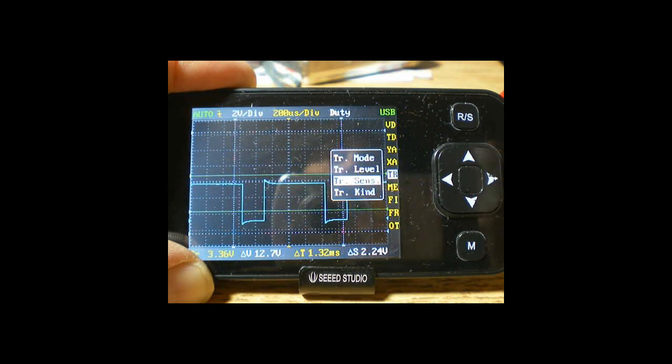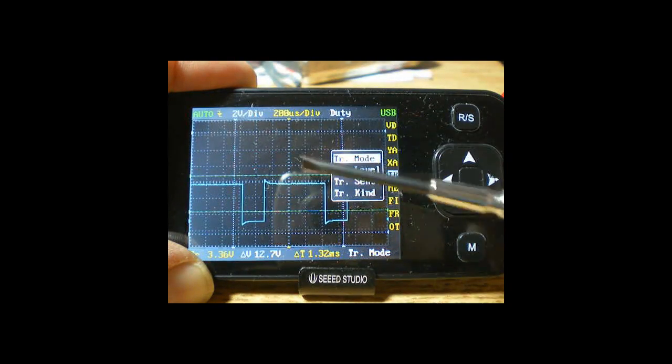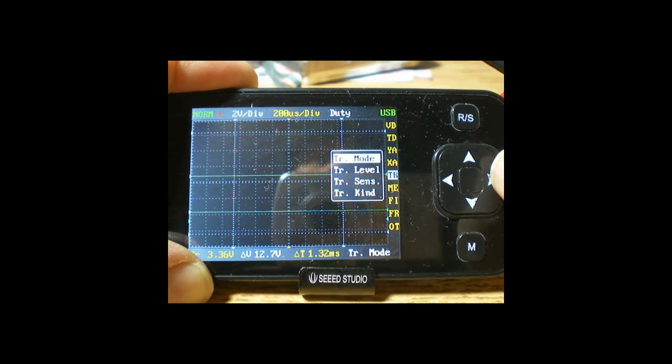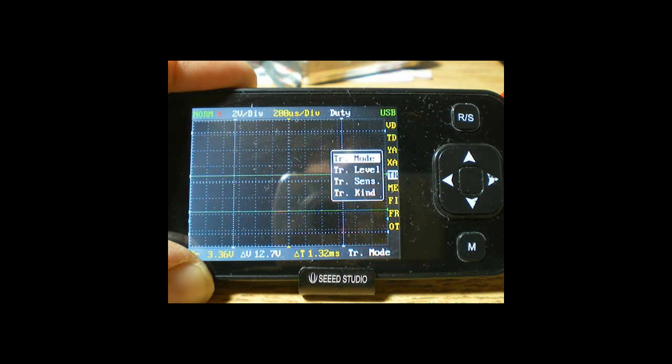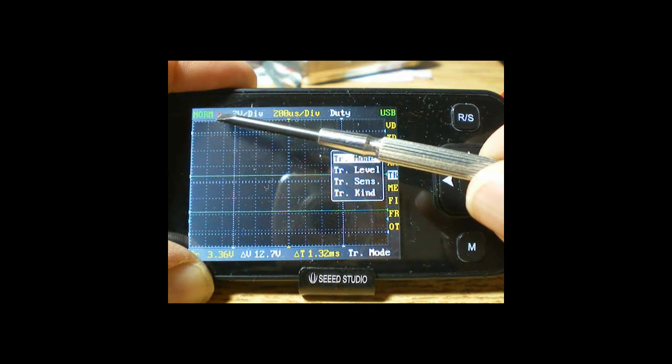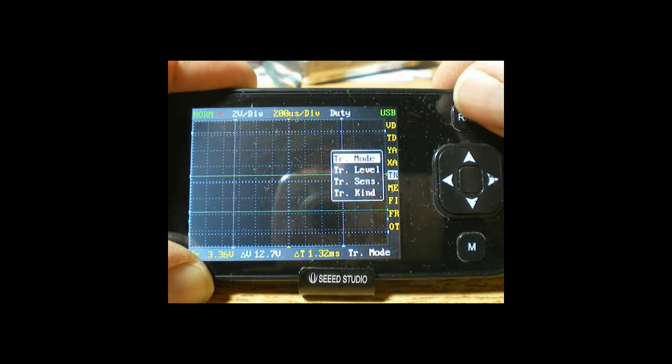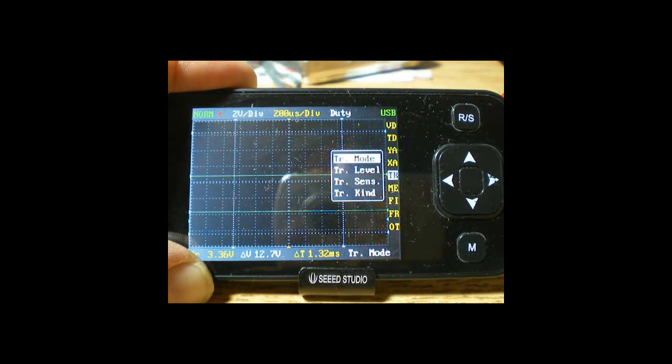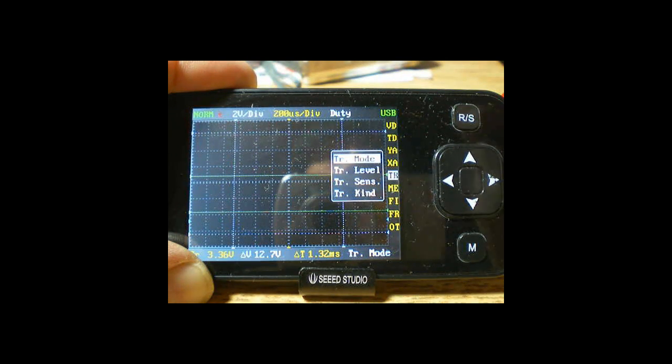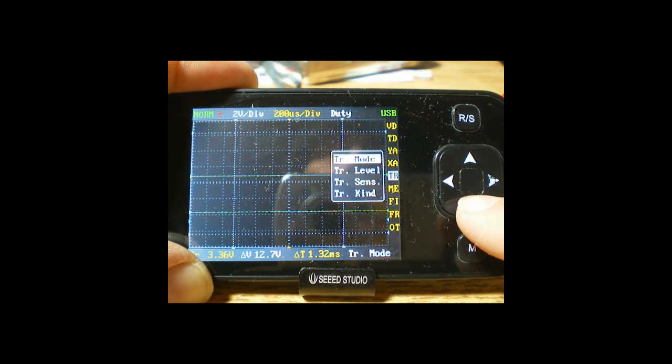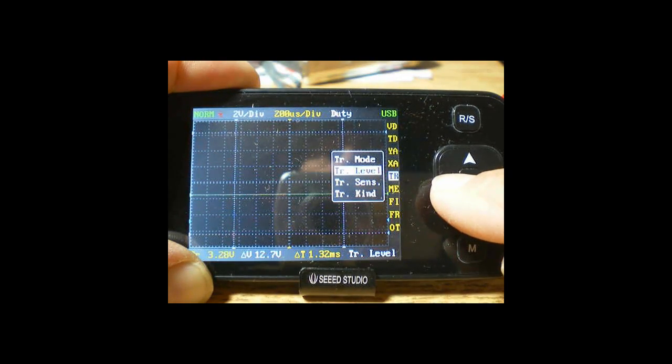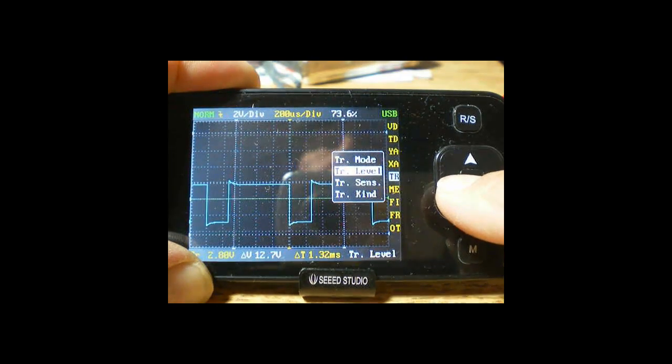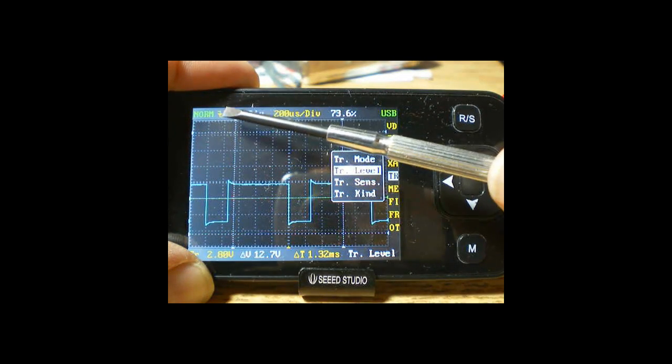And that's going to bring us to another part of the trigger system. We're going to look at the trigger mode for a moment. If we scroll up here to the trigger mode, auto is going to generate a sweep no matter what happens. So we're going to put it with the left and right arrow, we're going to put it in the normal mode, which means it needs triggers to keep generating sweep displays. Notice right here that the up-down arrow, in this case it's a down arrow, went red. That means there's no trigger available for the normal mode of triggering. We can force the trigger by stopping and running it, and it looked for one. Notice it flashes, watch it flash yellow. It looks for a trigger. It didn't find one, so it goes back to waiting. So it's basically waiting right now for a trigger because we're in a normal mode of trigger mode. If we move our trigger level down where it can find the trigger, and then lo and behold it finds the trigger and the sweep starts repeating itself.